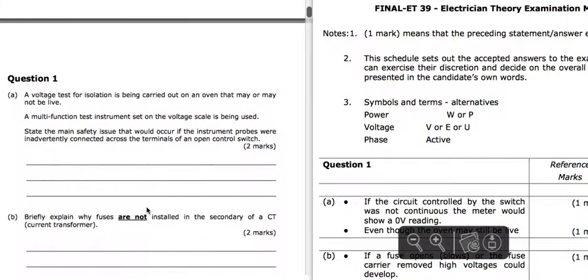Question 1 looks at isolation, and it says you've used a multifunction test instrument set on voltage scale. So you're measuring the voltage and you inadvertently measured it across the terminals of an open control switch. Now if we're going to test isolation, we don't want to go across switches, we want to be across the load or where we're going to disconnect it.